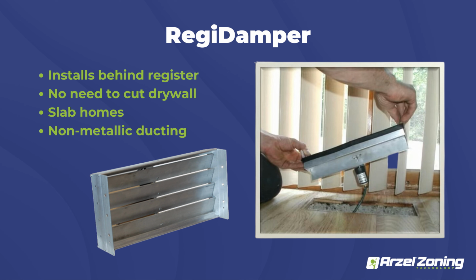The next damper is going to be our RegiDamper. This one also has its uses out there. Typically, if you have non-metallic, so if you guys got flex duct or something like that, you got a couple rooms in the home that you just don't have great access to. This specific damper itself is a galvanized aluminum, so it basically sits underneath your register grill. You can see it in the bottom picture there. Once it's installed, you can still put on your register cover so you don't see the metal fins when it's installed. There are a couple of drawbacks to the RegiDamper because it is not a gasketed seal.